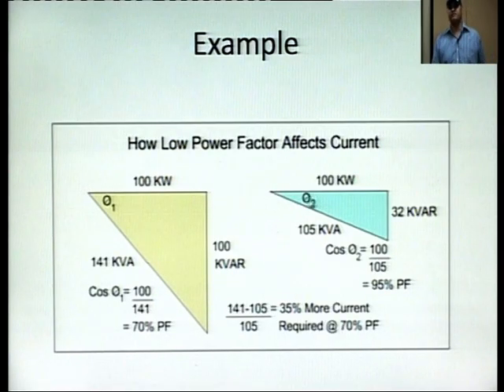Now the kVA rating changes. There will be less kVA: instead of 141 kVA, it is 105 kVA. If we calculate the power factor, it is 100 divided by 105, which is 95%, or a 0.95 power factor. Now to see how much current is required, we take the kVA of the first system, 141, minus the kVA of the second system, divided by the kVA, and we can say that 35% more current will be required if we use 100 kVAR instead of 32 kVAR. So this is how low power factor affects the current.